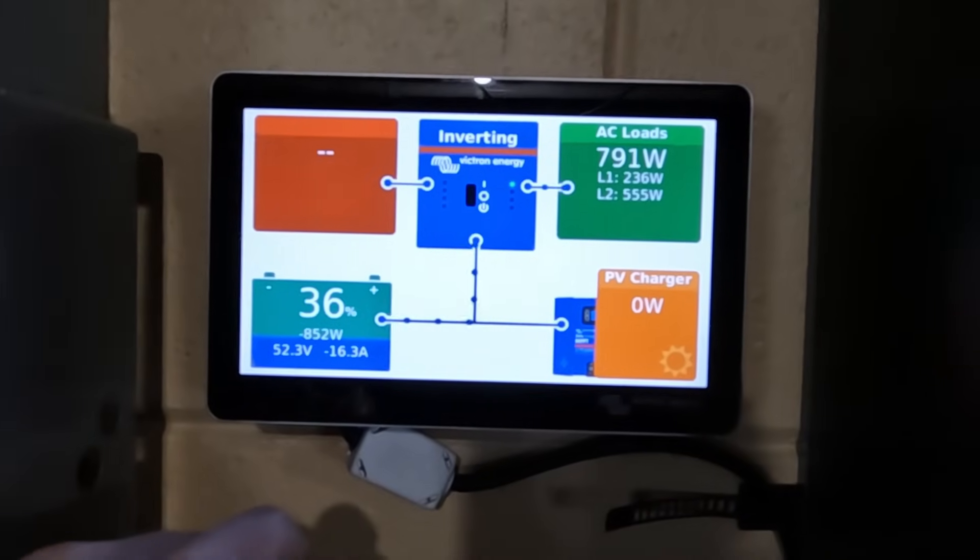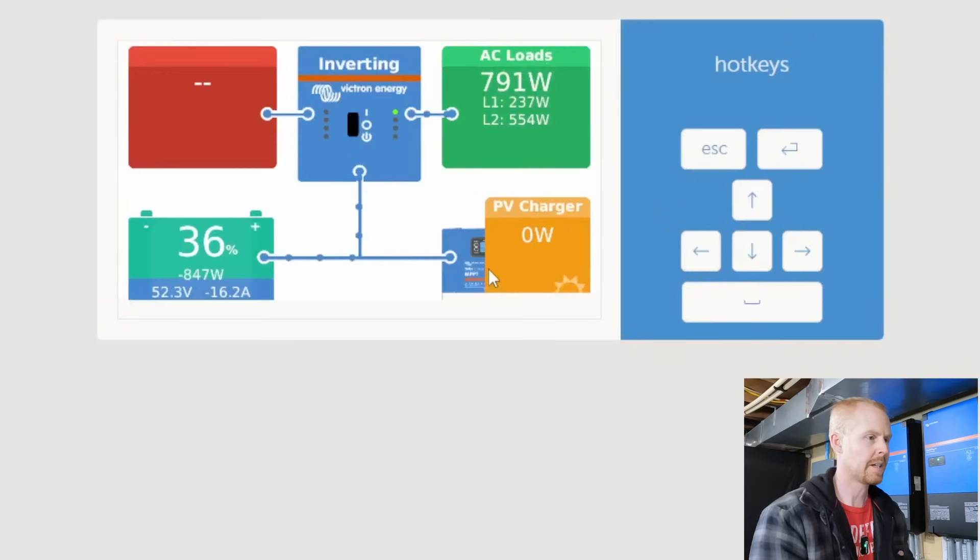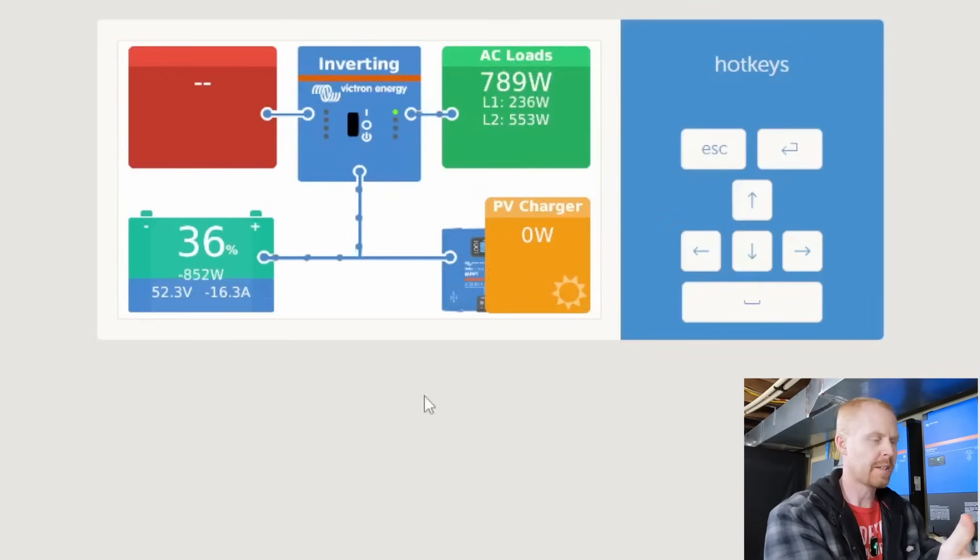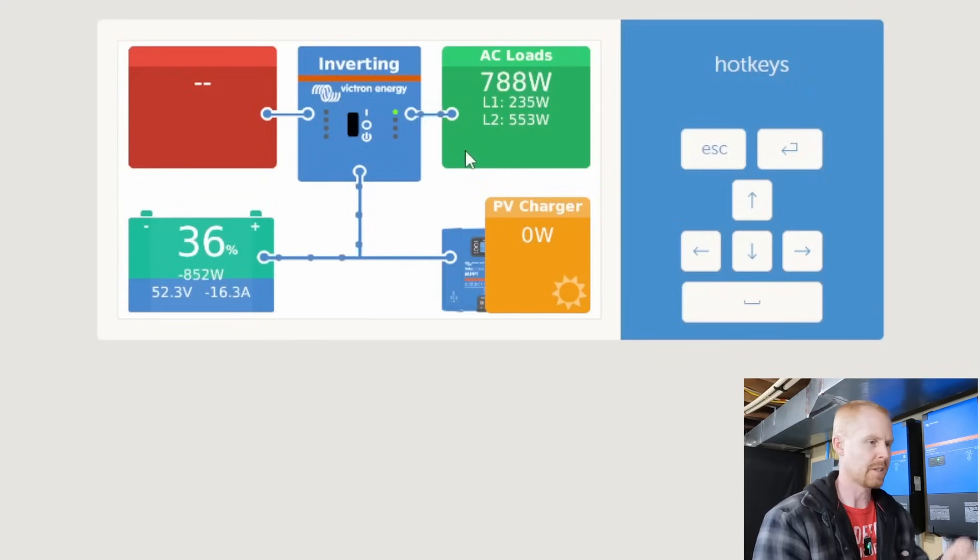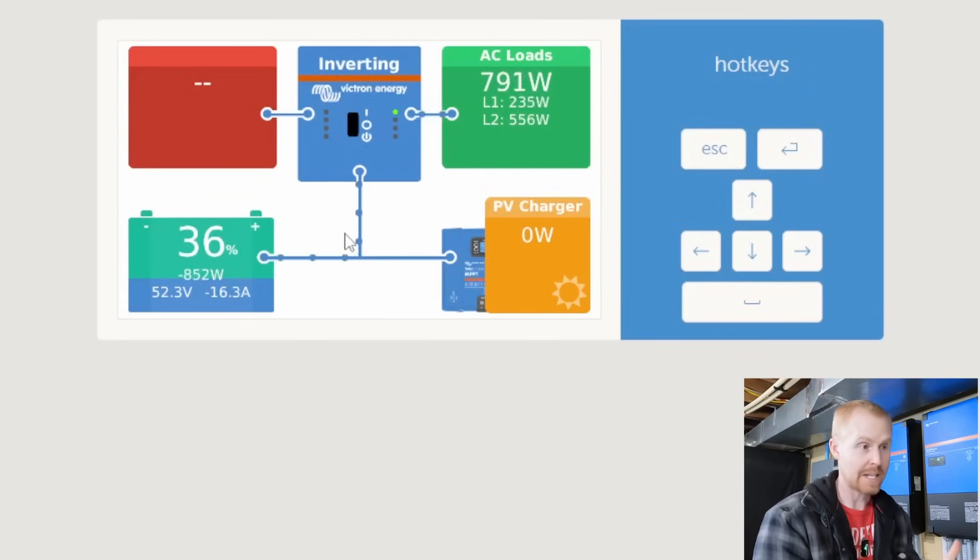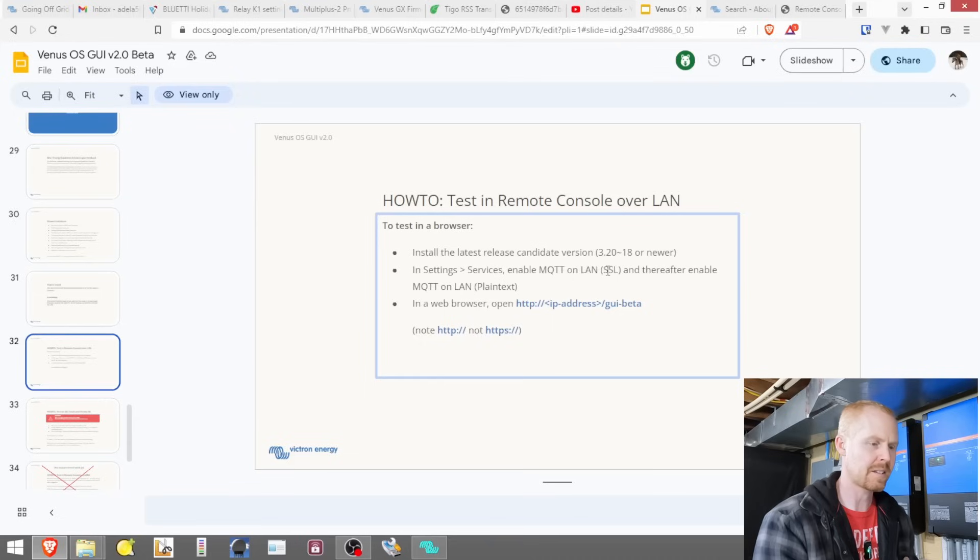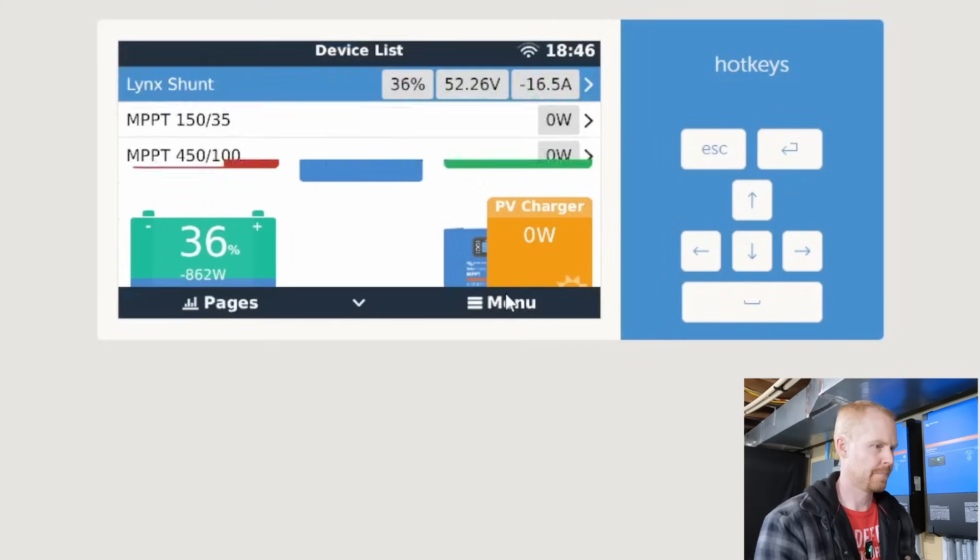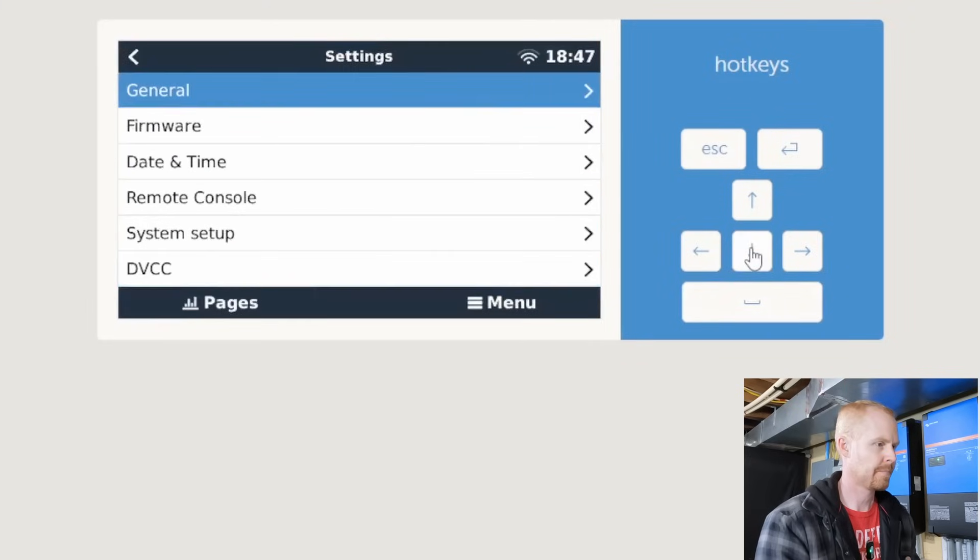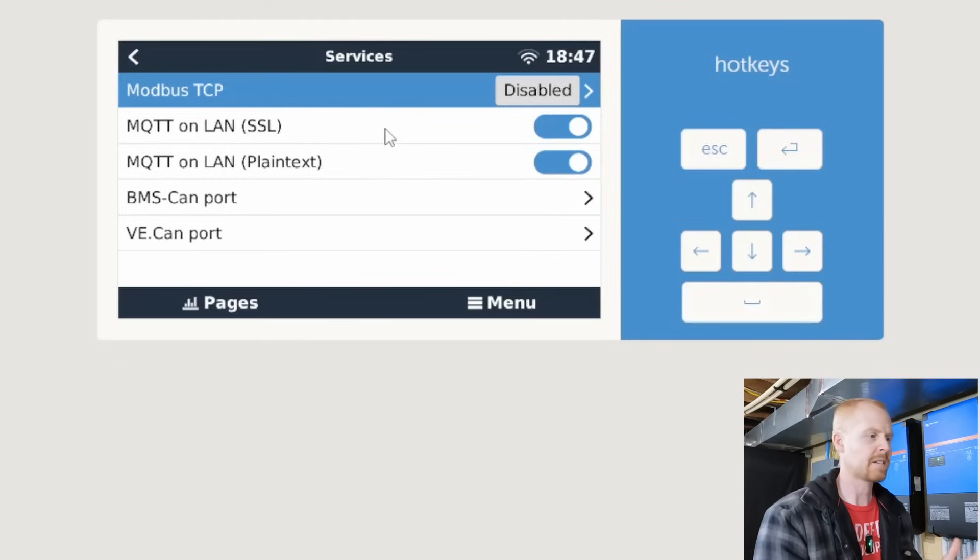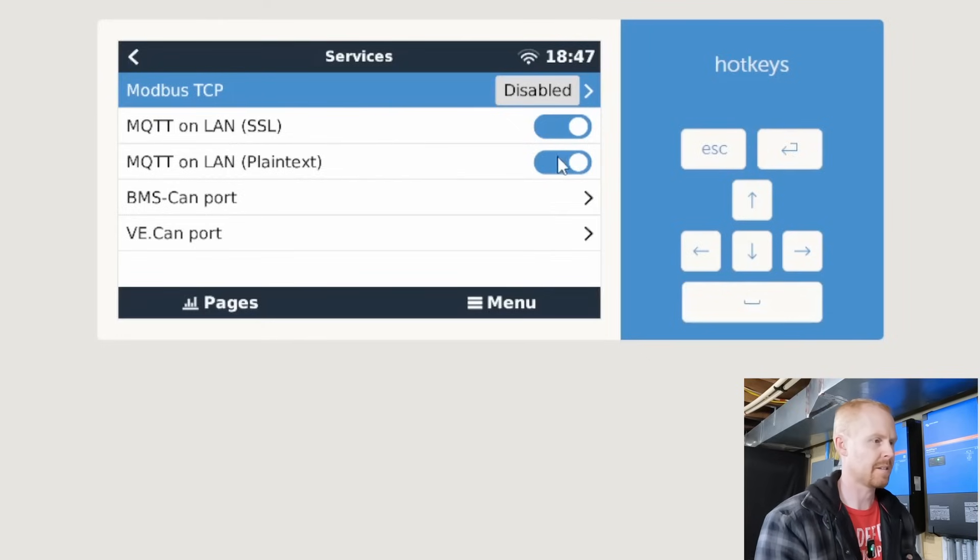And our Cerbo is back up and running. We'll reconnect over here. So you can see the GUI mods changes are all gone. We don't have all the extra information that we used to have. It did come back up, so that's great. So the next thing we need to do is we need to come into settings, services, enable MQTT on LAN, the SSL, as well as the plain text version. So we'll come over here, menu, settings, services. And it looks like at some point in time I've already enabled this, MQTT on LAN, SSL, and plain text.